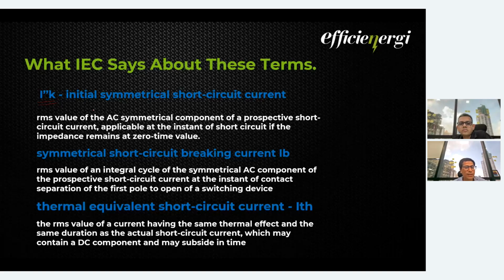It is basically when the fault is occurring and the impedance remains the same at the zero time value. Zero time means T0, T minus 0 and T0, T plus 0. We'll be talking in those terms. So at T0, the RMS value of the AC symmetrical component. Again, this is only talking about the AC symmetrical component of the prospective short circuit current applicable at the instant of short circuit.